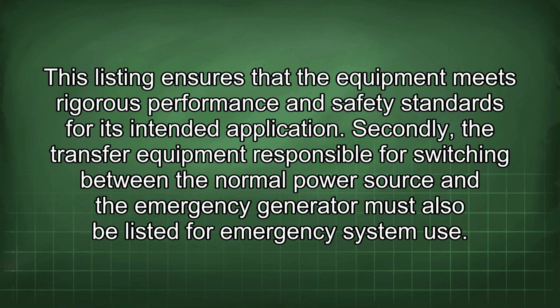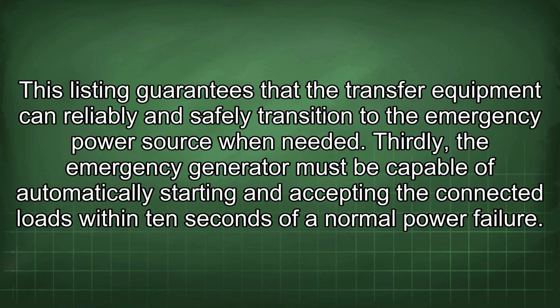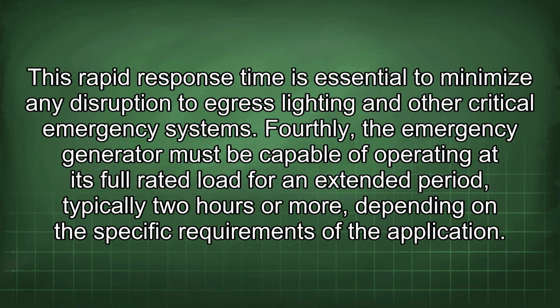Secondly, the transfer equipment responsible for switching between the normal power source and the emergency generator must also be listed for emergency system use. This listing guarantees that the transfer equipment can reliably and safely transition to the emergency power source when needed. Thirdly, the emergency generator must be capable of automatically starting and accepting the connected loads within 10 seconds of a normal power failure. This rapid response time is essential to minimize any disruption to egress lighting and other critical emergency systems.